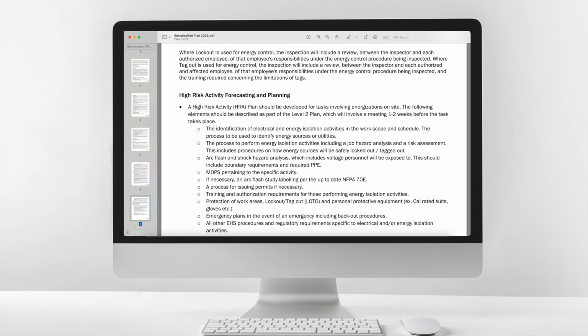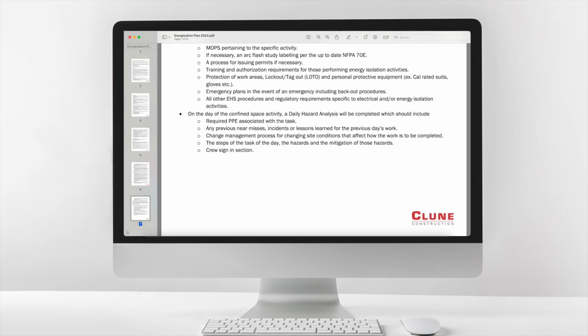Arc flash and shock hazard analysis, which includes voltage personnel will be exposed to. This should include boundary requirements and required PPE. MOPs pertaining to the specific activity. If necessary, an arc flash study labeling per the up-to-date NFPA 70E. A process for issuing permits if necessary. Training and authorization requirements for those performing energy isolation activities. Protection of work areas, lockout, tagout, LOTO, and personal protective equipment, such as arc-rated suits, gloves, etc. Emergency plans in the event of an emergency, including backout procedures. All other EHS procedures and regulatory requirements specific to electrical and/or energy isolation activities. On the day of the confined space activity, a daily hazard analysis will be completed, which should include required PPE associated with the task.